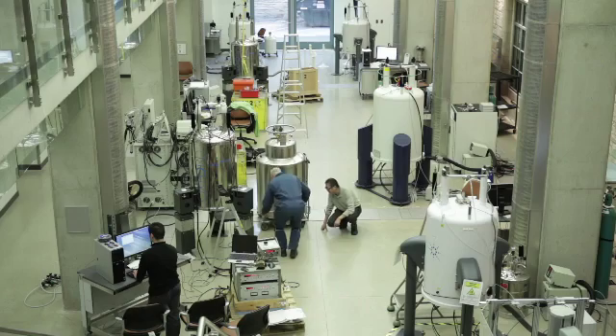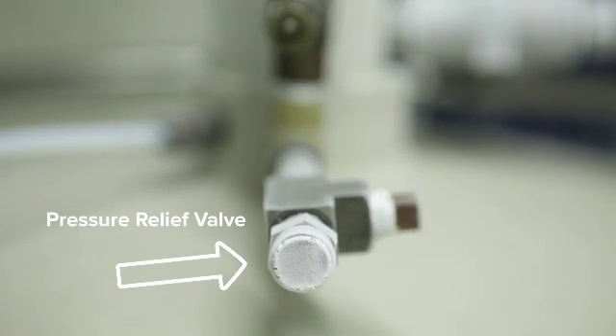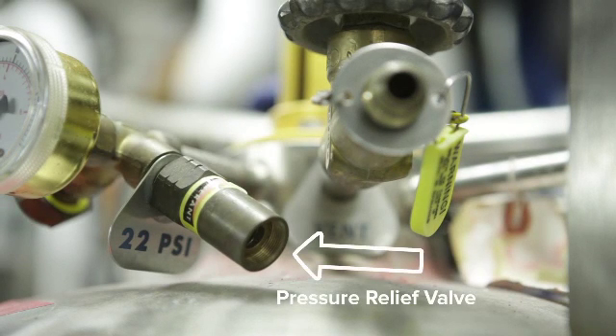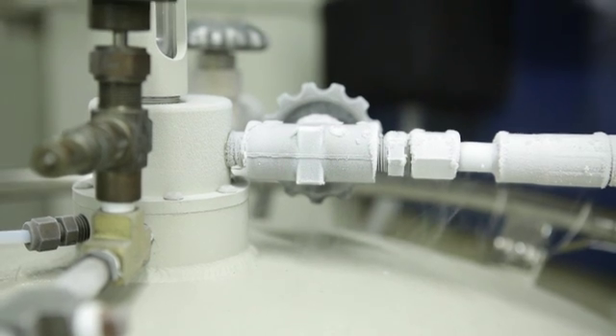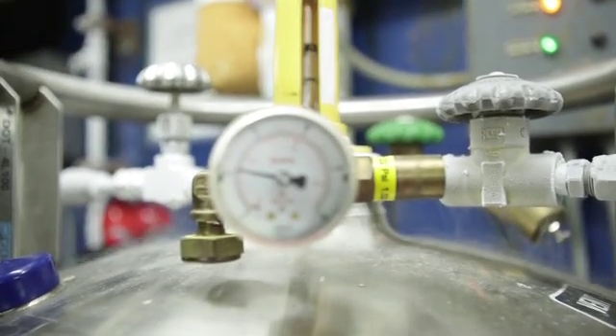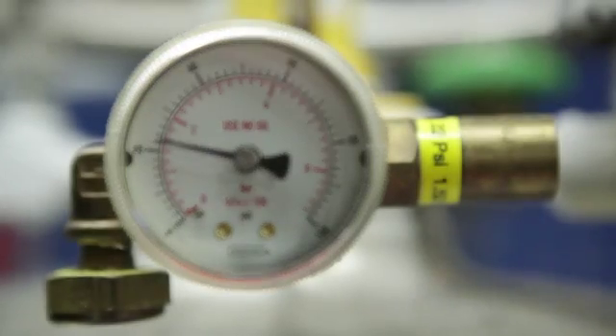If the cylinder is dented or damaged during transport or use, the tank must be professionally inspected to ensure it may continue to be used safely. Cylinders are equipped with pressure relief valves that will open and close to release gas at preset pressures. The primary pressure relief valve opens at the lowest pressure and regularly vents excess gas. A slight hiss from a liquid nitrogen tank indicates normal operation. A small gauge installed on the cylinder may show the pressure inside the tank, and this reading should be equal to or less than the setting of the primary pressure relief valve.